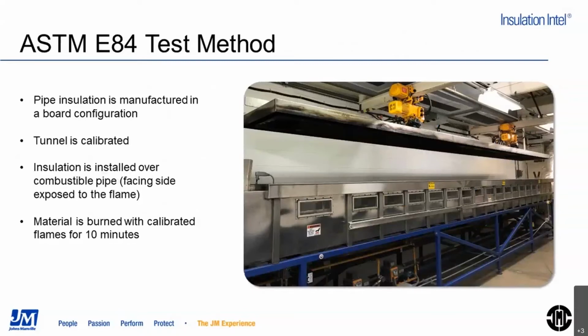Now we're looking externally, and this is the tunnel that we have at our research facility. It's a large-scale test. The specimens installed in this tunnel are 2 feet by 24 feet. Obviously, it can be hard to get such long pieces, so we can use sections of it. That's basically what we've been doing for this testing, especially since our pipe insulation comes in 3-foot sections. Those are the sections that we've had installed in the tunnel. The insulation is tested in the flat configuration, and obviously the pipes are round, so how do we do that? There's a procedure, ASTM E2231, which tells us how to produce test specimens specifically for this test so that they're representative of the pipe insulation. You can really think of it as a flattened, squished pipe insulation.